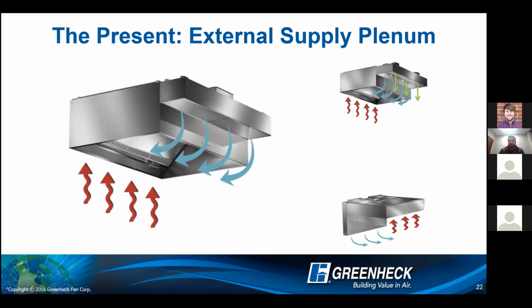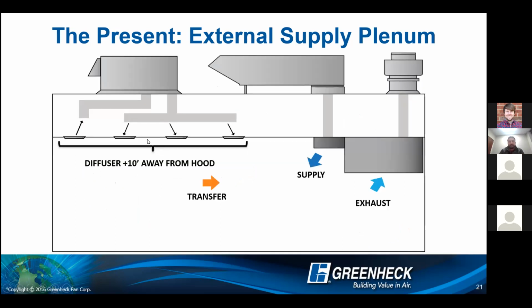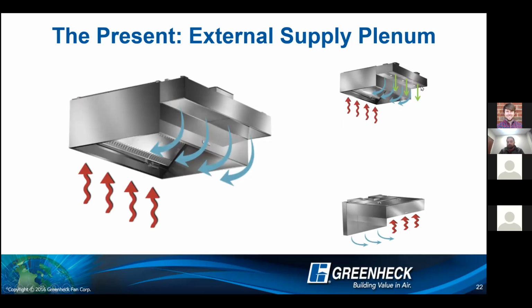That's the most common. The next product that you'll see in the marketplace is in this upper right-hand corner. We have what's called a split ASP. Now, this is a good solution if you can't have diffusers 10 feet away from the hood, but you still want to utilize that rooftop unit for your transfer air or for your pressurization. So you would still have your dedicated makeup air, which is designated by these blue lines coming in the front. And then this front plenum is an insulated, typically 10-inch wide plenum that can accept air from your rooftop unit, and it can be placed within 10 feet of the hood because it's coming out as downdraft. So it doesn't have any possibility of coming out of a diffuser and disrupting the capture of the hood. So that would be an option. Again, that's the split ASP option.